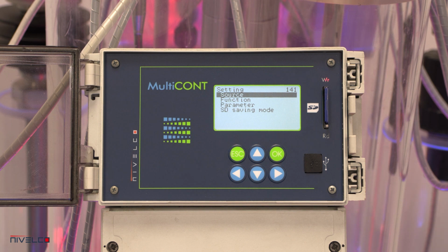The unit logs the ID of the transmitters, the primary value, and 3 additional values. Time-controlled logging stores entries after a specified amount of time. Event-controlled logging stores entries when a set condition is met.